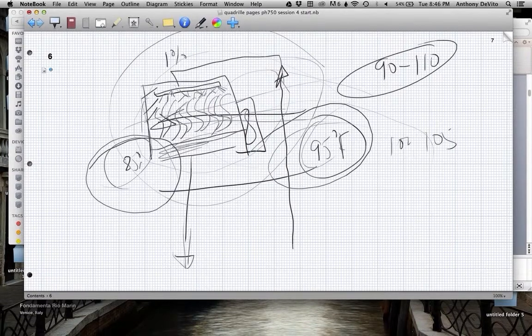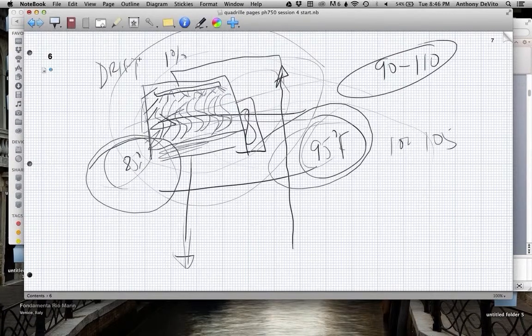They put these devices either on the top or the side where the air exits the cooling tower. They're called drift eliminators. And what does that mean? That means they're supposed to eliminate the droplets of water from getting blown out of the cooling tower. They're not 100% efficient. You stand next to one of these things, you get wet. You feel some spray from it. What's in that spray? Droplets of water. And what's in those droplets of water? Legionella. Now, interestingly enough, Legionella is ubiquitous in nature. It's in a lot of places. You find it in lakes, ponds, and so on and so forth.